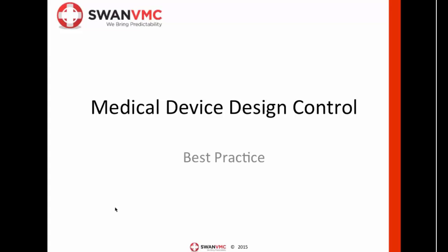with the manufacturing piece in the traceability table engaged. And then what you could do is put your receiving and inspection in there and actually drive the testing on the production floor directly through Polarion. Okay, now we're in the middle of the construction of the product, and our intended use of Polarion is to control the use of and the building of the product. Now it's a subject of process validation. We're going to have to think about process validation. So I think it really depends. The validation, if you do a validation, could be very simple or it could be really complicated. So it just depends on what you're using it for.